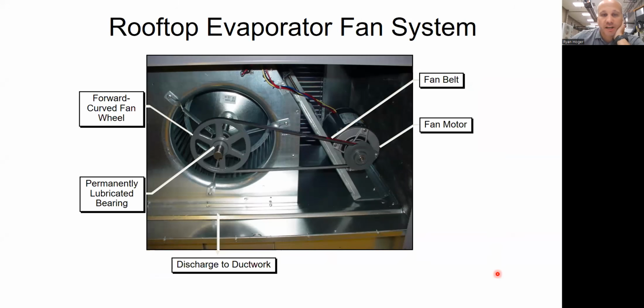So just ask. This is the indoor, what we would call a blower section. It's the evaporator fan because it's the one that draws the air through the evaporator. Sometimes we call it a blower. Sometimes we call it a fan. We always call it something different in order to confuse you. Most of these are belt driven, but not all of them.